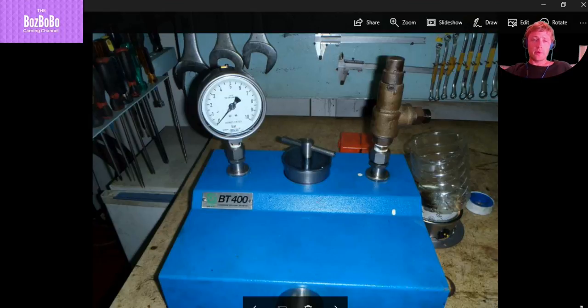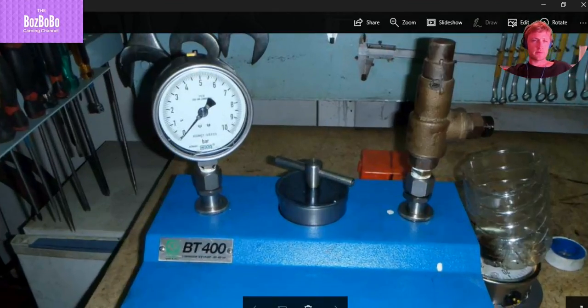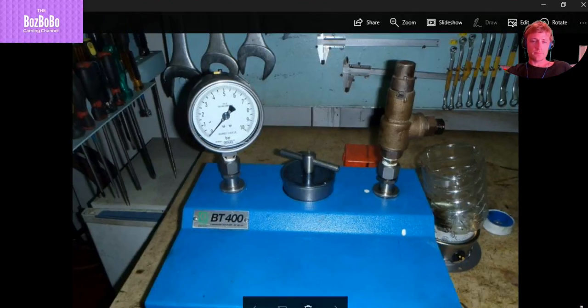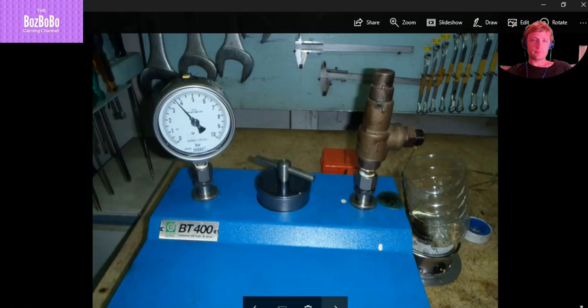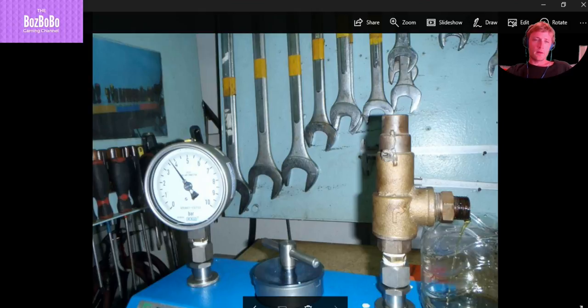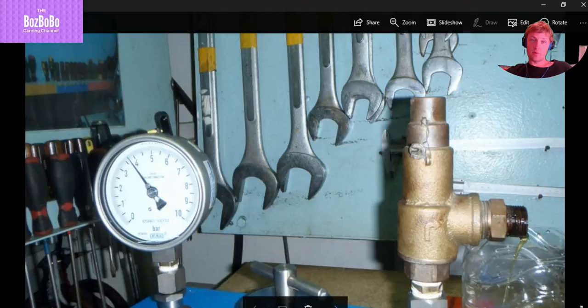Let's say that the pressure opening is five bars or four bars. Let's see the picture here. It's 3.6. You can see that 3.6, about 3.7. The safety valve is opened and here we have oil running.